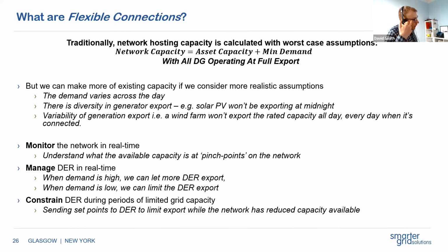And so what you need to do is monitor the network in real time. That's previously been quite difficult to do because of the size of distribution networks. It can be quite expensive to put a lot of monitoring out. You've got to manage the DER in real time, so you've got to make sure your DER are smart enough to be able to be controlled. And you need some centralized system to be able to work out when those generators need to be curtailed, when those generators need a command sent to them.